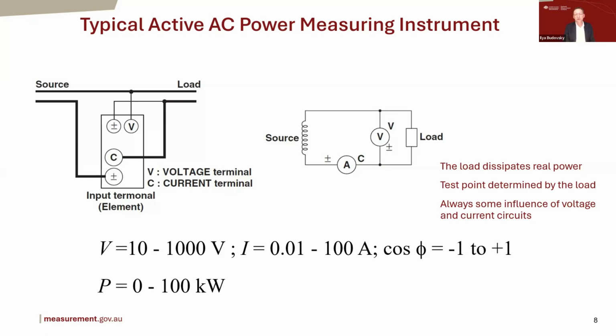Of course, it's very difficult to use this particular configuration for calibration purposes, because the load dissipates real power. If it is, for example, 1,000 volts and 100 amps, which is quite typical within the capability of the wattmeter, this would be 100 kilowatts. So it's very, very difficult to make an adjustable load for such power, and also environmentally unfriendly.